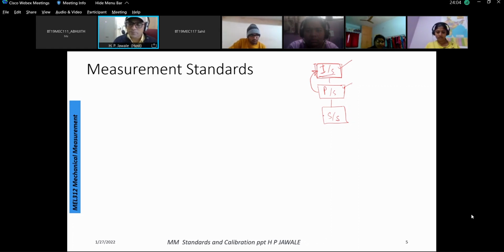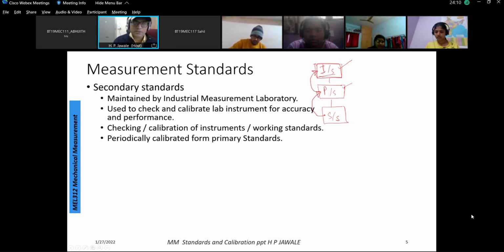Each secondary standard placed in a proper laboratory is compared with the primary standard, and again its accuracy is maintained. So the secondary standard is maintained at the industrial measurement laboratories. There can be different names and tags for these measurement laboratories, but basically it is kept in a particular location of the region in a country. It is used to check and calibrate the lab standard. Now next, it is the working standard or lab standard.